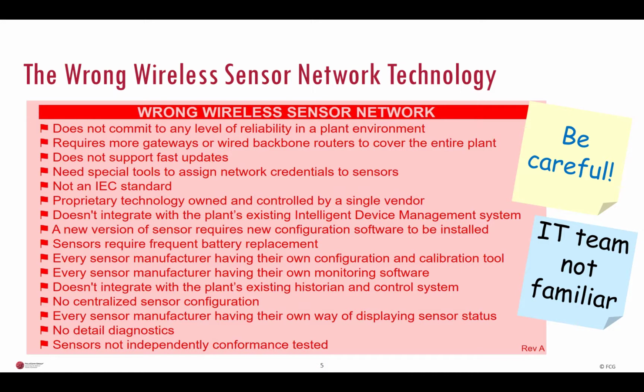The wrong wireless sensor network technology is not reliable, requires a lot of costly infrastructure, is slow, needs special tool to commission in many steps, is a proprietary technology which has risks of obsolescence, cannot use intelligent device management software used for wired instrumentation, has short battery life. Every sensor manufacturer has their own sensor configuration and calibration tool and their own monitoring software. There is no Modbus or OPC to integrate with your existing DCS, PLC, historian, or other software. There is no centralized sensor configuration software. And you only get status, but no advanced diagnostics. For instance, no vibration spectrum. So be careful. You will have to live with these limitations, if you pick the wrong technology.